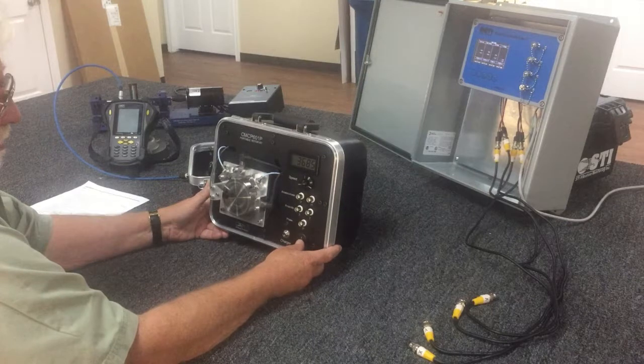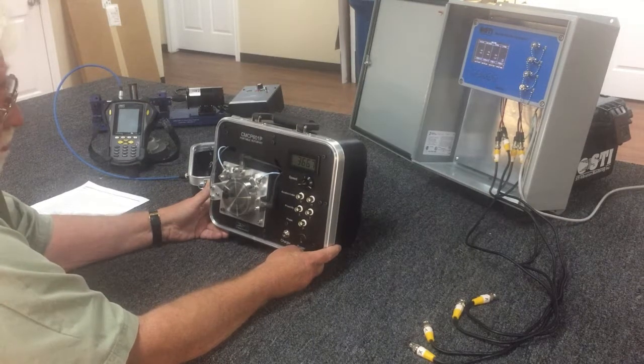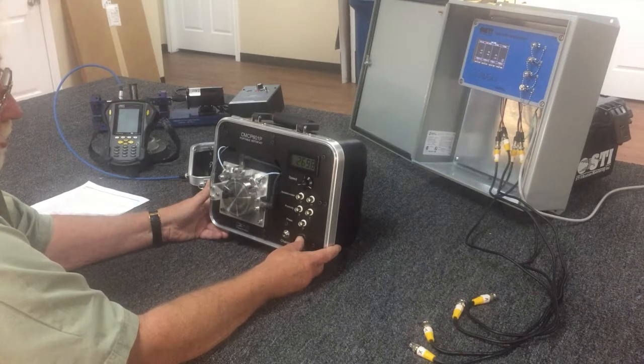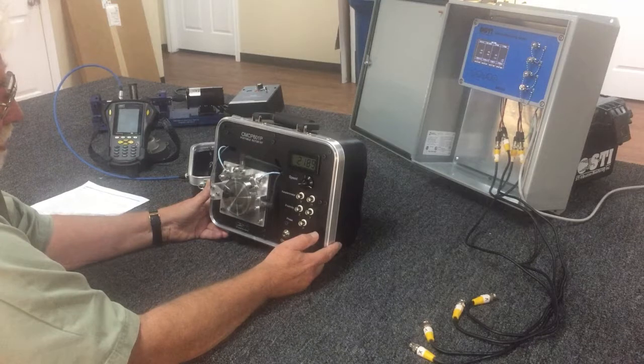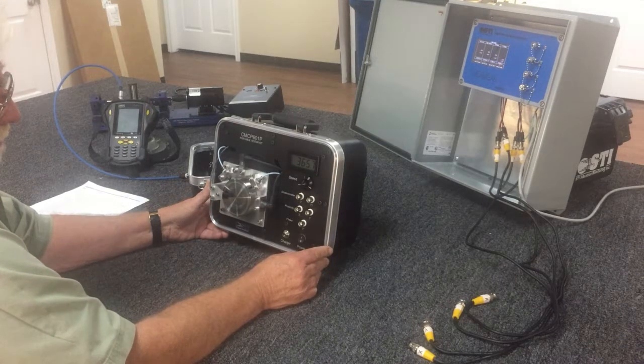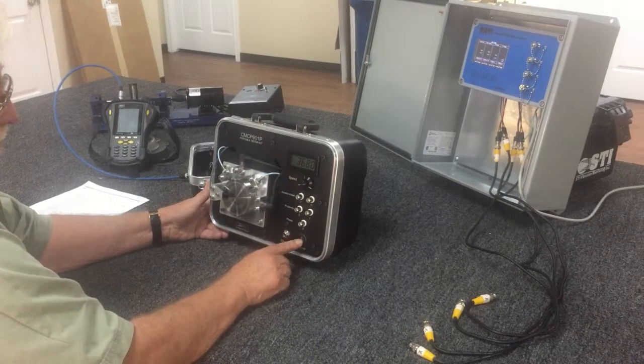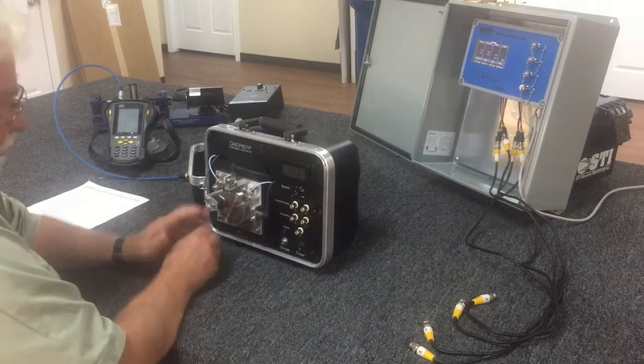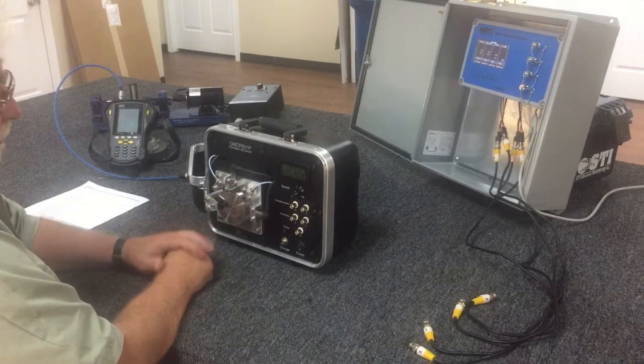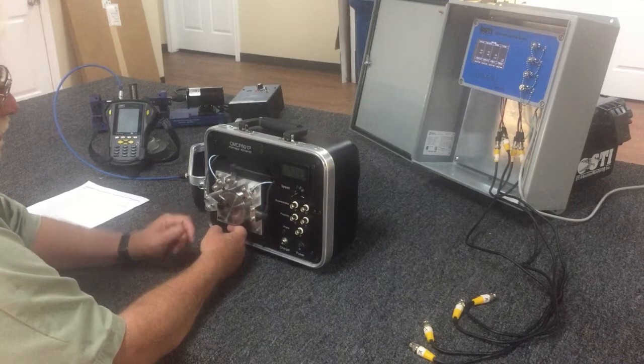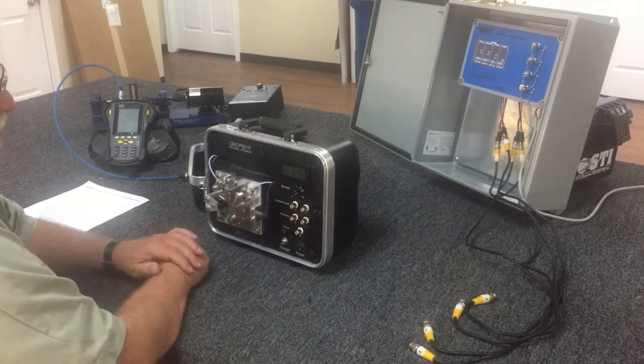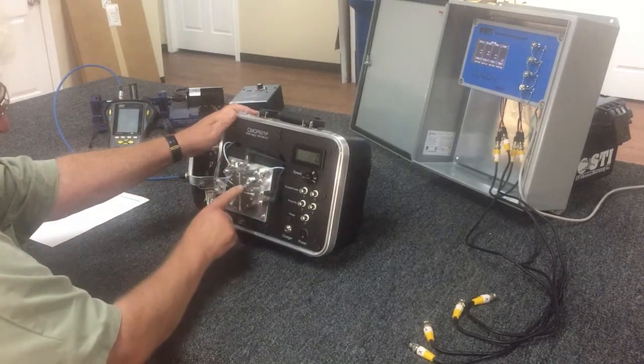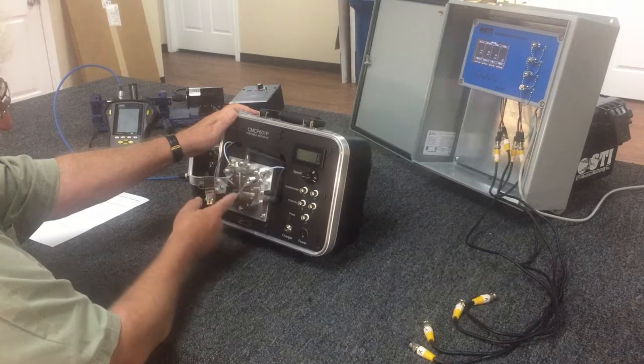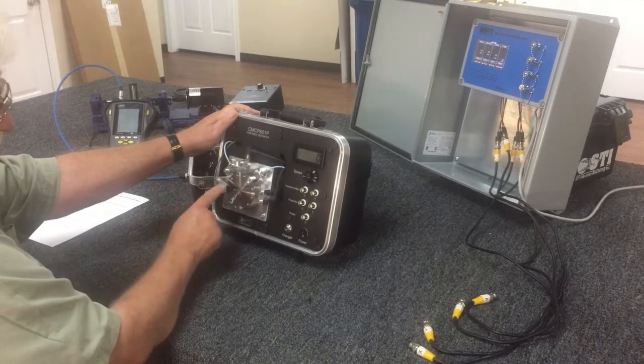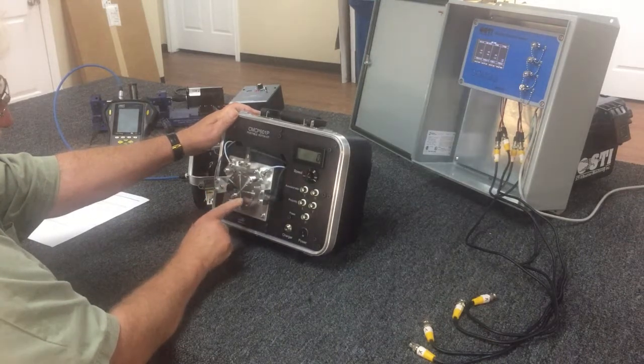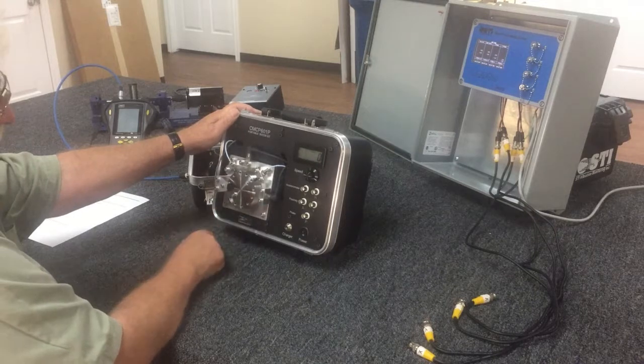And you'll notice one thing about it is when you turn off, it is a digital motor. It's a 3-phase, 8-pole motor, digitally controlled. It'll go right back to where it was when you turn the switch off, as you'll notice by the speed. Okay, over on this side we have our rotating mass, which we're going to wait for it to wind down just a bit. Don't put your finger on the top because there's a phase bump going around. Here's our rotating wheel. You'll notice we have a little metal washer on top that triggers the built-in phase angle detector. This is a once per turn detector. So as it goes under here, you'll get your blip for doing balancing or phase on an oscilloscope.